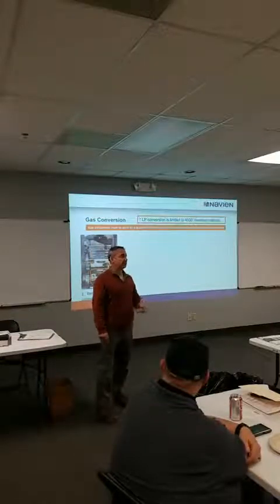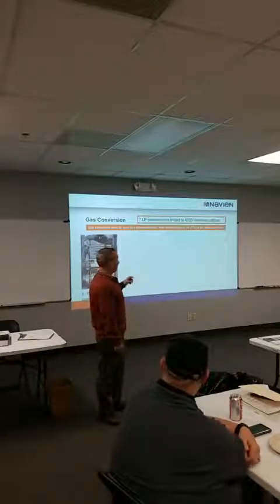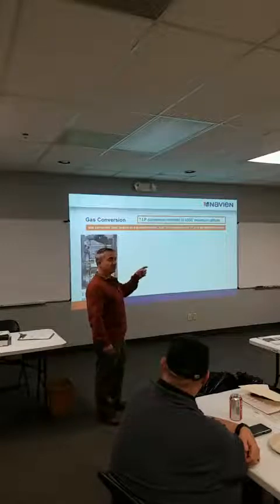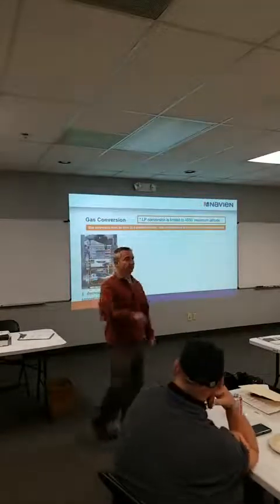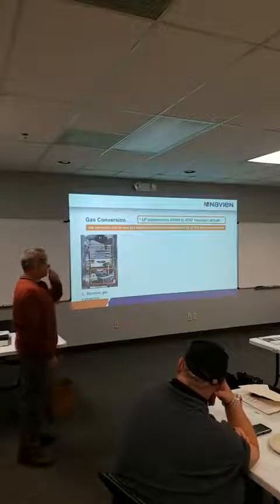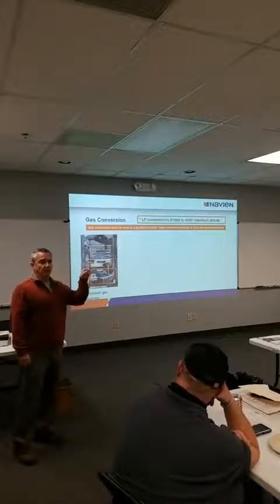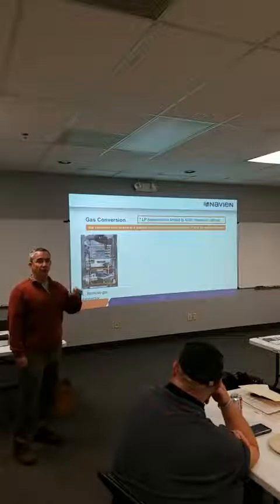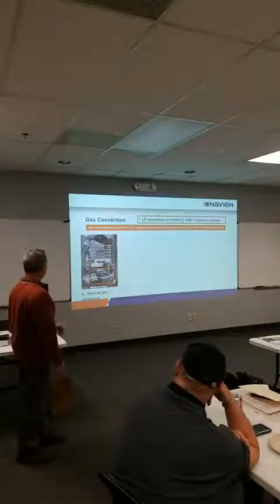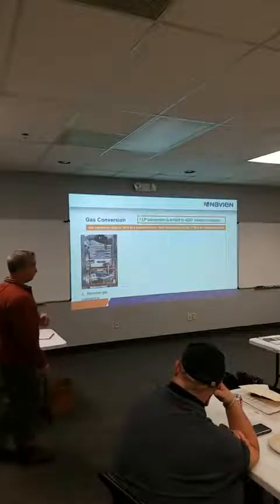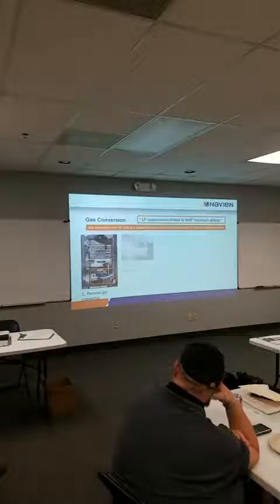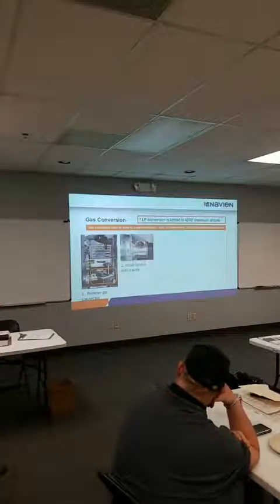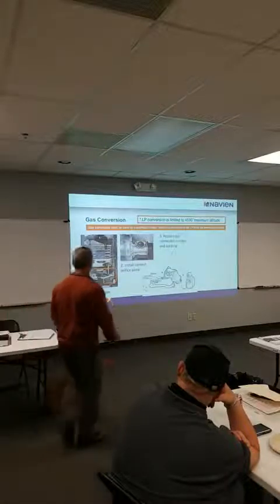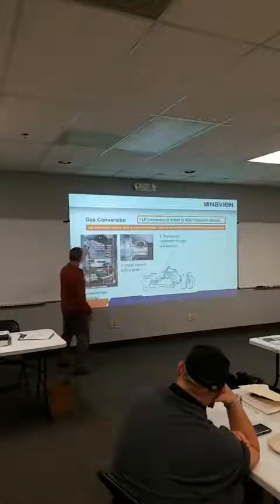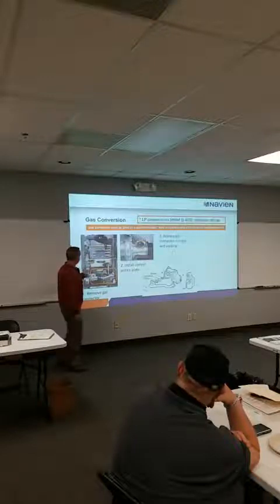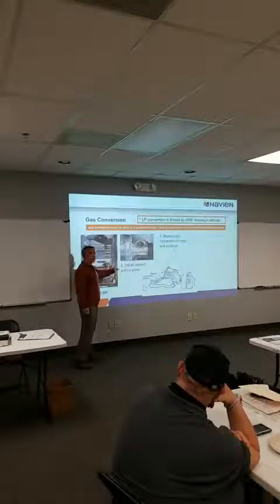We give you the specs in the installation manual for either the test on the gas valve or the test at the vent. For propane too, the specs? Yes. You'll see in the book, by model number, specs for natural gas and propane right next to each other. All of our units are field convertible to propane. They all come natural gas in the box. We give you a little conversion kit inside the unit. Usually it's in a little plastic bag on the left side of the unit. There's usually a little spare parts bag on the right side of the unit inside.